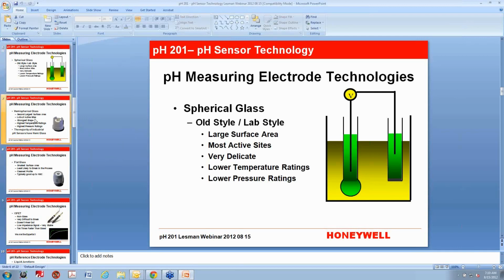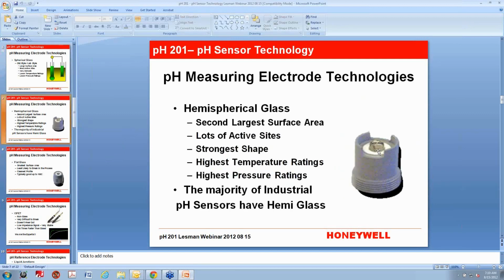The next one up is the hemispherical glass. This is a pretty decent picture of hemispherical glass. So basically it's a half of a ball or a half circle, and it is welded or annealed to, again, a glass stem. It has the second largest surface area, so it still has a lot of active sites, but not as many as the spherical glass. This is the strongest shape, and the reason it's the strongest shape is because if you think about this half ball being welded to a hollow glass stem, that weld angle is 180 degrees.